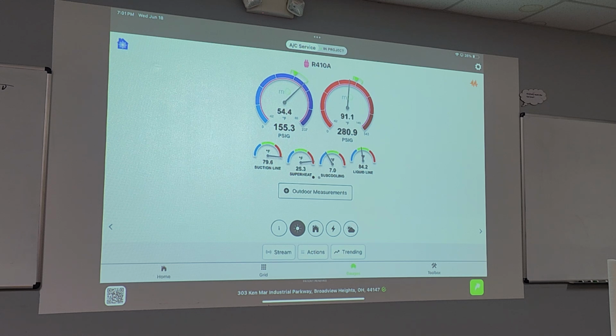So, other thing, I don't have much field experience with this, just the high humidity load. You've got a super high latent load, you're making a ton of water. It's an extremely high heat load on this thing, even though it's not that hot out temperature-wise. All the water on that evaporator puts a ton of load on it, so maybe the valve's wide open and it just can't feed enough to satisfy the load?